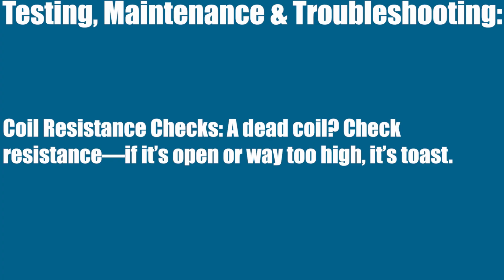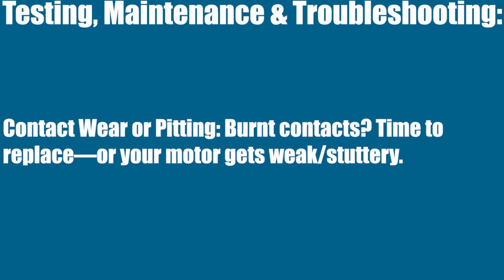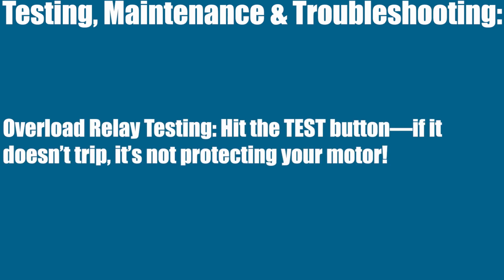Testing, maintenance, and troubleshooting. Things that go wrong, here's how to catch problems early. Coil resistance checks. A dead coil, check resistance. If it's open or way too high, it's toast. Contact wear or pitting. Burnt contacts, time to replace, or your motor gets weak and stuttery. Overload relay testing. Hit the test button on it, and if it doesn't trip, it's not protecting your motor.